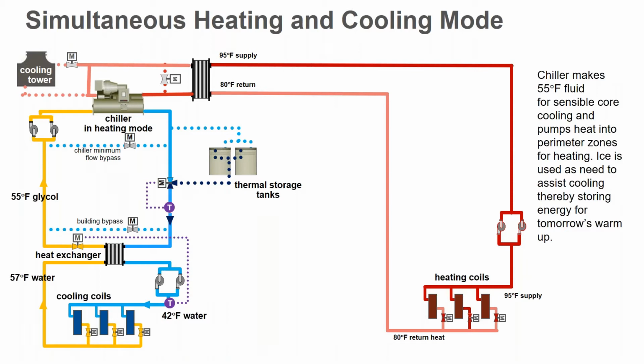In the simultaneous mode, you're going to run the chiller. You're not going to be doing anything with the tanks. And if the core of the building is too warm, you are going to cool the building as you normally would, and the energy from the cooling coils is going to go to the chiller. It's going to get heat pumped up to a usable level and go into the heating coils of the building. So you can use that chiller whenever there's a simultaneous heating and cooling mode. And if it wasn't the same balance, you could use the tanks if you needed more heat, or use the tanks if you needed less.